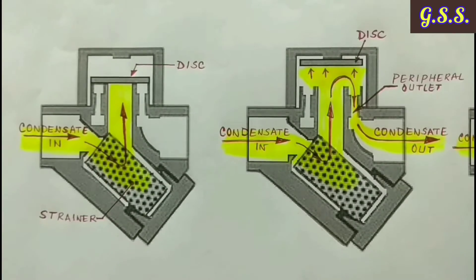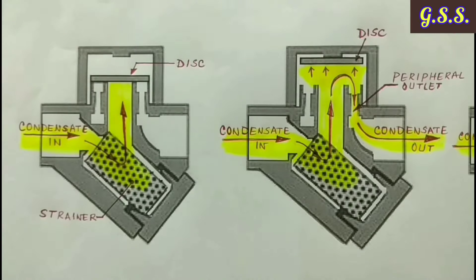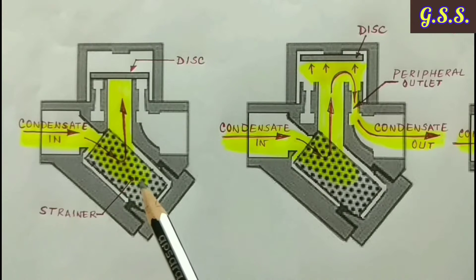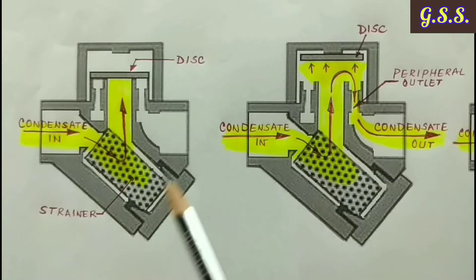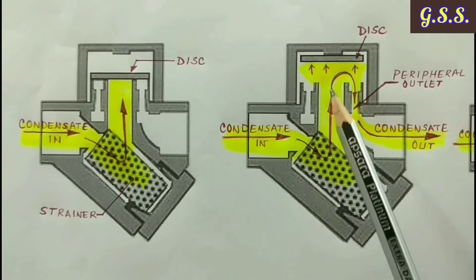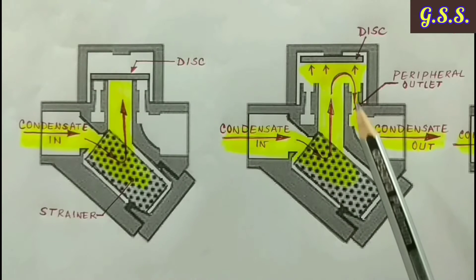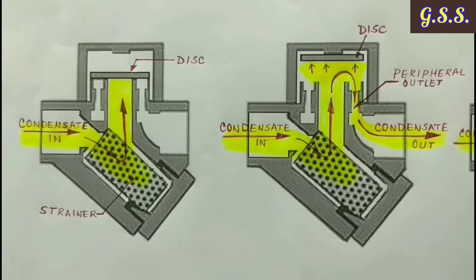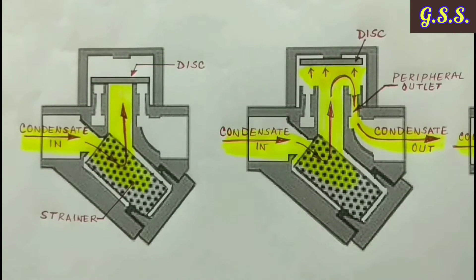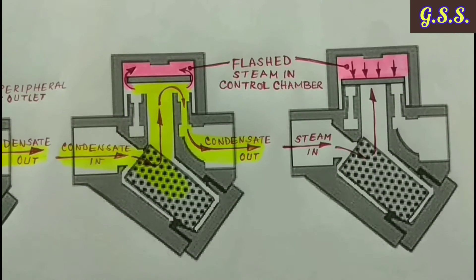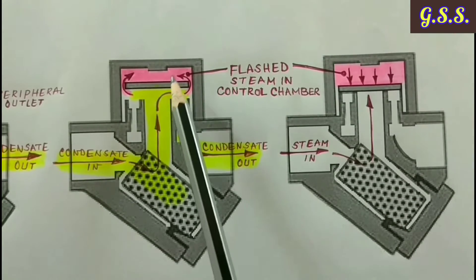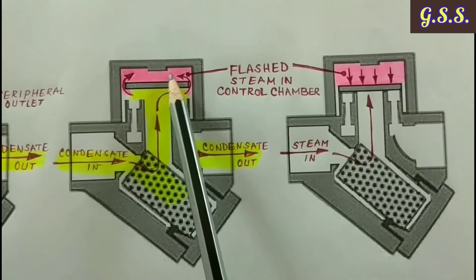Now we will see how a thermodynamic steam trap works. At startup, air and condensate enters the trap through the strainer where particles are screened. Then condensate pushes up the disc and discharges through the peripheral outlet. While discharging, due to the narrow peripheral area, its velocity increases and pressure decreases, and some part of the condensate flashes to steam. This flash steam is accumulated in the control chamber.